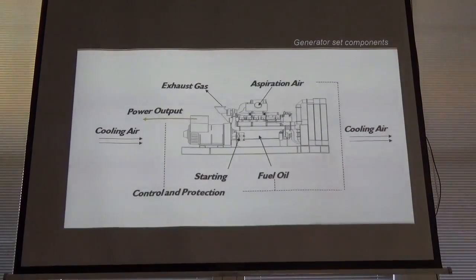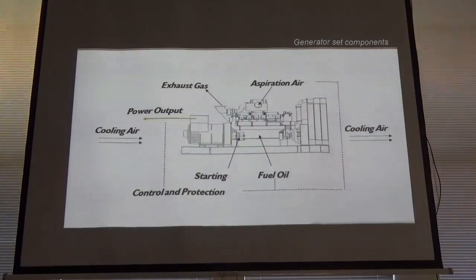Through that cooler matrix, you might then get a heat pickup, the heat dump across that for the intercoolers and main jacket cooling. You might get an increase in temperature of about 30 degrees centigrade. So either way, you're talking 70s, 80 degrees centigrade discharge temperature, which needs to be considered when you're at maximum ambient or design ambient. So all these things again need to be considered. You don't want to be discharging air where someone's walking. That's just a little bit too much of a large hairdryer really.